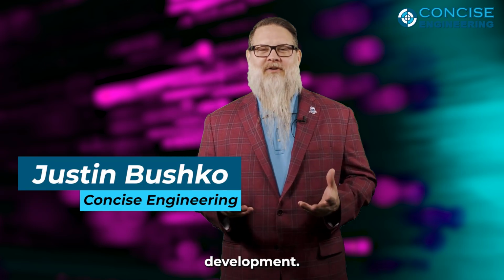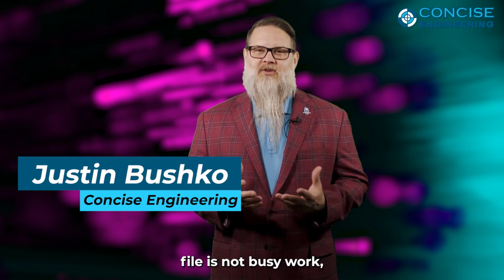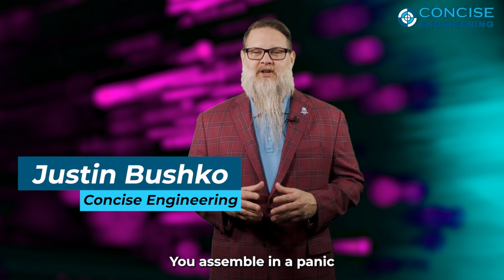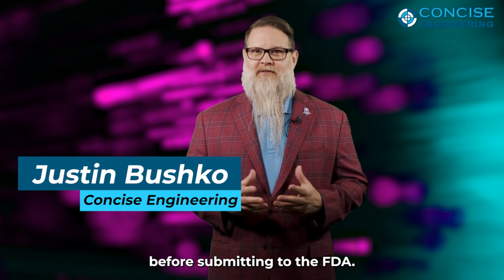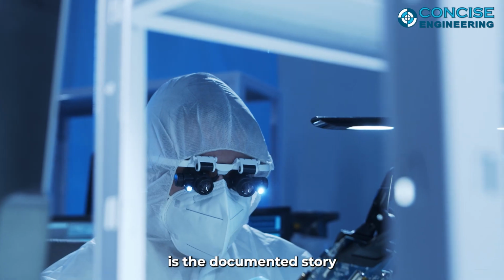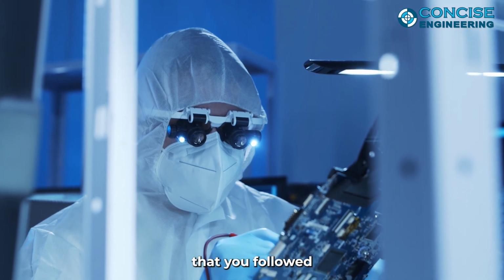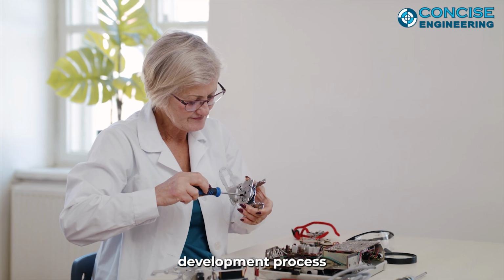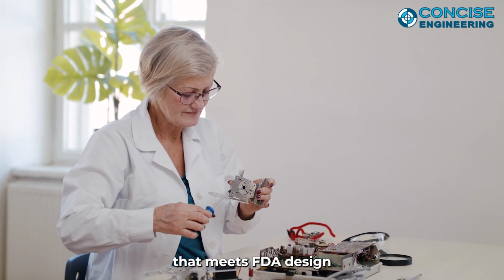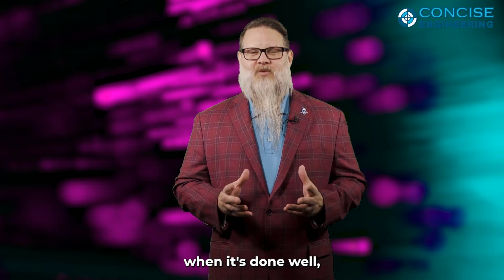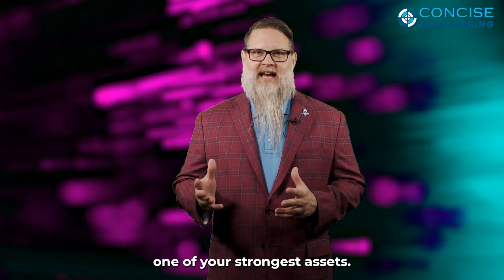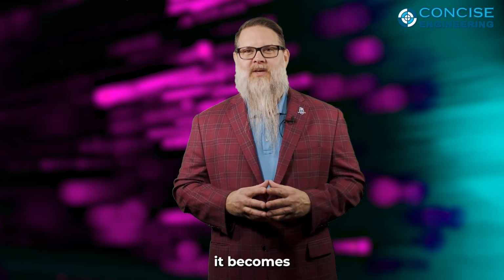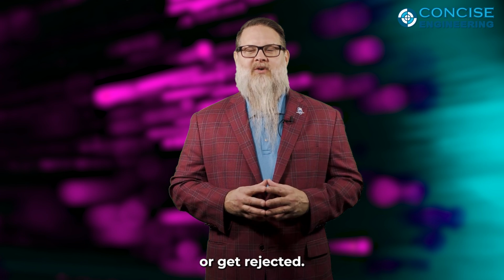In medical device development, the design history file is not busy work, clerical overhead, or something you assemble in a panic before submitting to the FDA. The DHF is the documented story of your design, the proof that you followed a structured, controlled, and traceable development process that meets FDA design control requirements. When it's done well, it becomes one of your strongest assets. When it's done poorly, it becomes one of the biggest reasons submissions stall or get rejected.